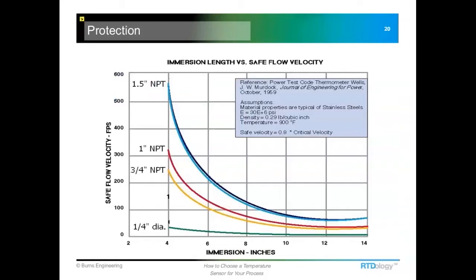Now the wake frequency issue, when you have a cylindrical object in a high flow rate, this turbulence can form on the downstream side of the cylindrical object. In this case, it's a thermal well. And if the oscillation of that turbulence matches the resonant frequency of the thermal well, it can start to vibrate. So this is going to typically happen at some pretty high flow rates, depending on the style of thermal well. And this table shows where that can happen. If we have a 1/4 inch diameter temperature probe installed in the process, we can see it's roughly maybe 25 or 30 feet per second is where that probe at 4-inch immersion, that's this number right here, will start vibrating. And when it starts to vibrate, bad things happen.